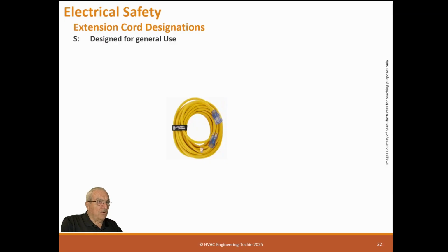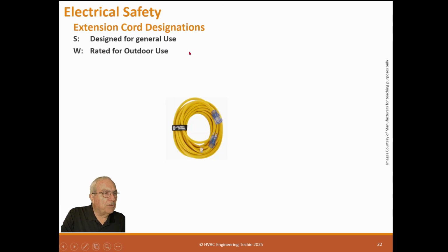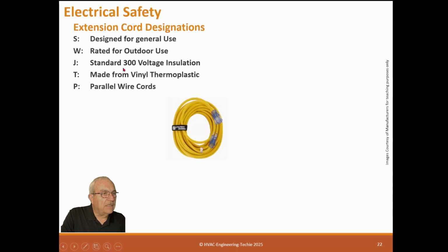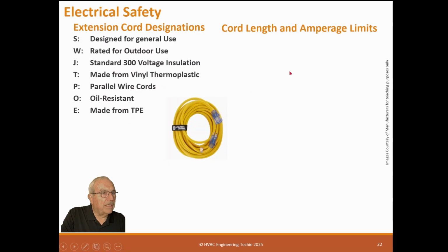So extension cord designations: they come in different designations in case you need a special one for what the job you're working on. S is designed for general use. W is rated for outdoor use. J is standard 300 volt insulation. T is made with vinyl thermoplastic. Normally we have 600 volt, by the way. Parallel wire cords. Oil resistance. E is made from TPE.